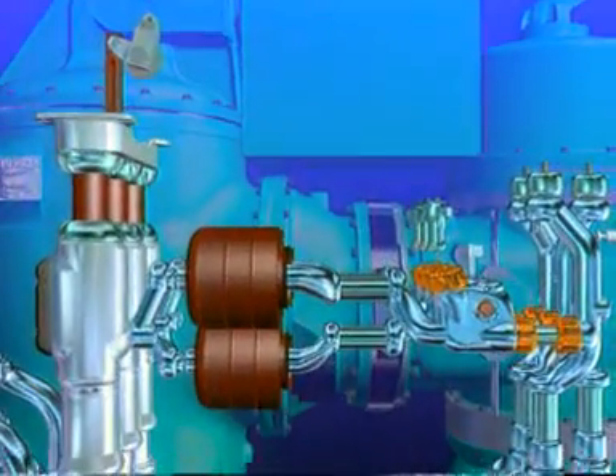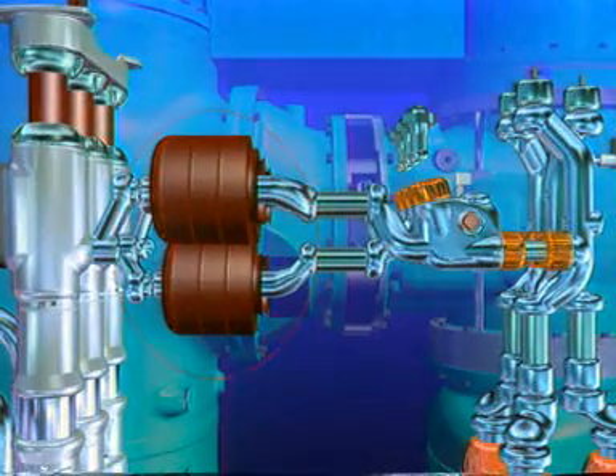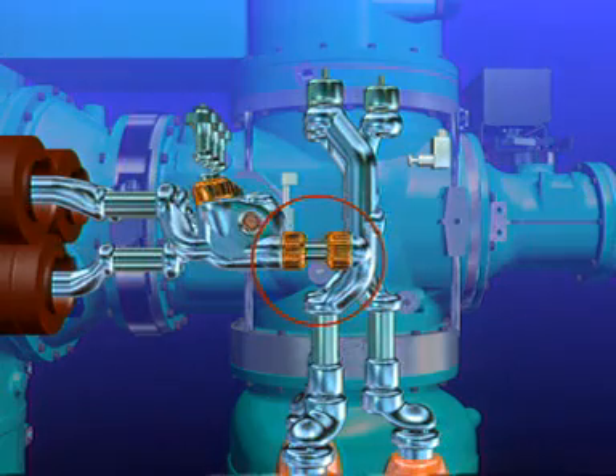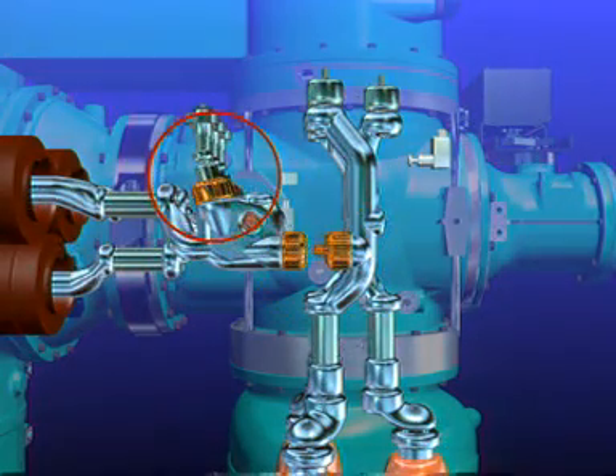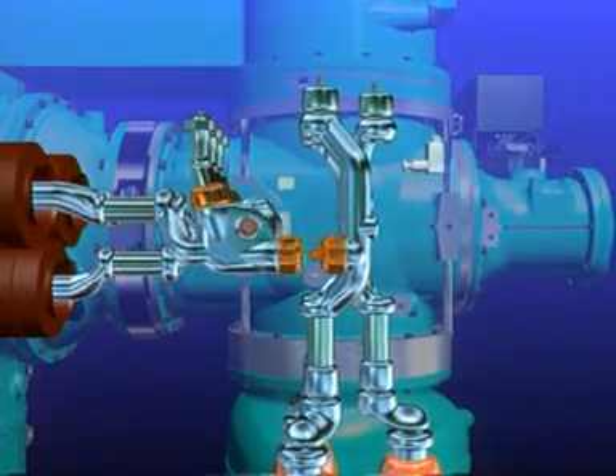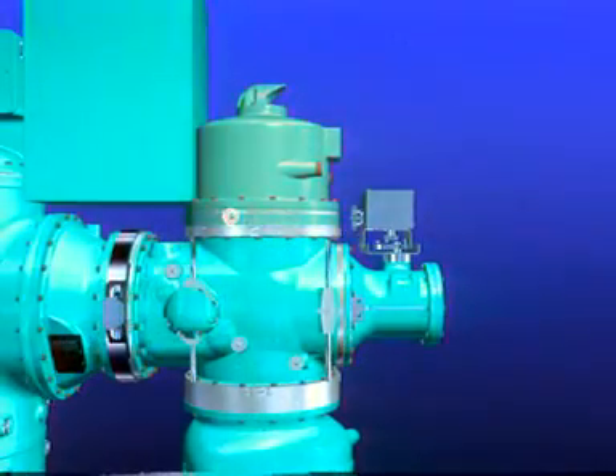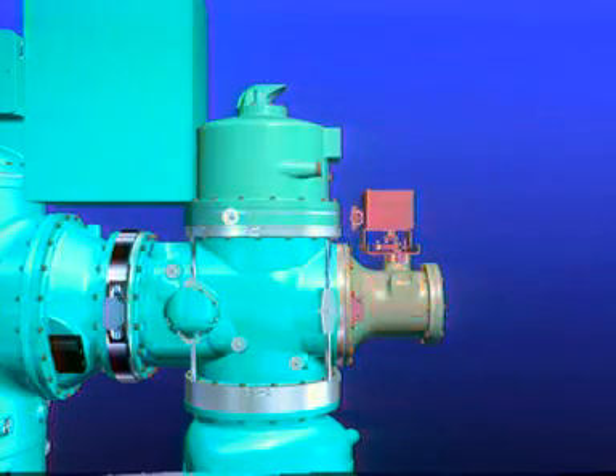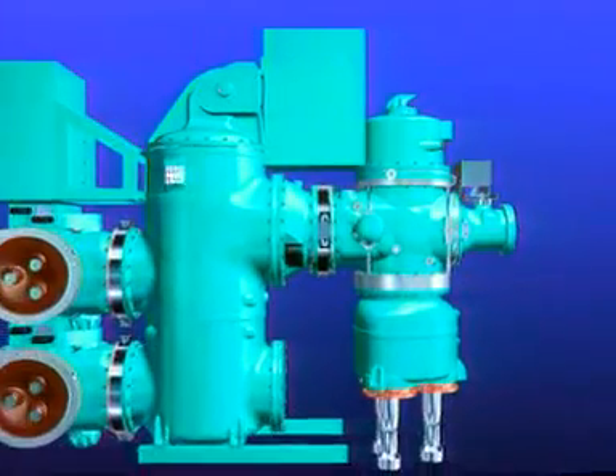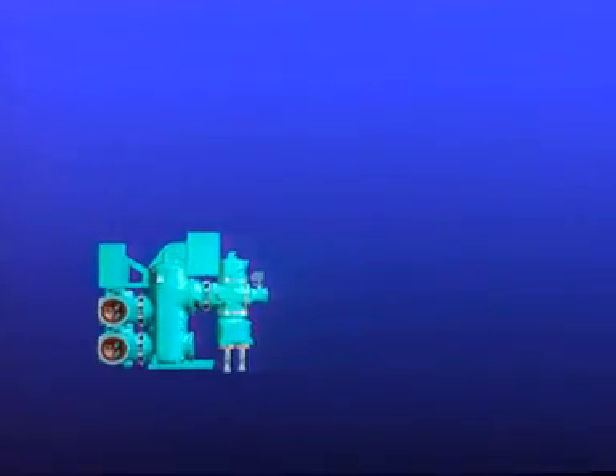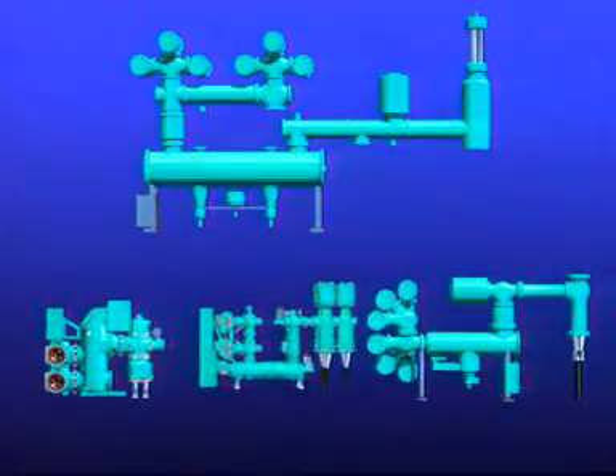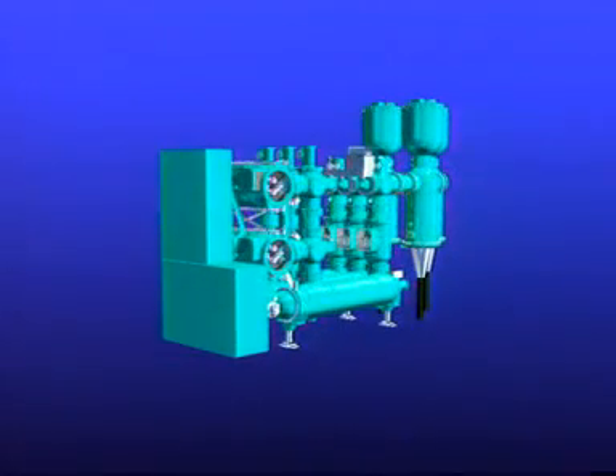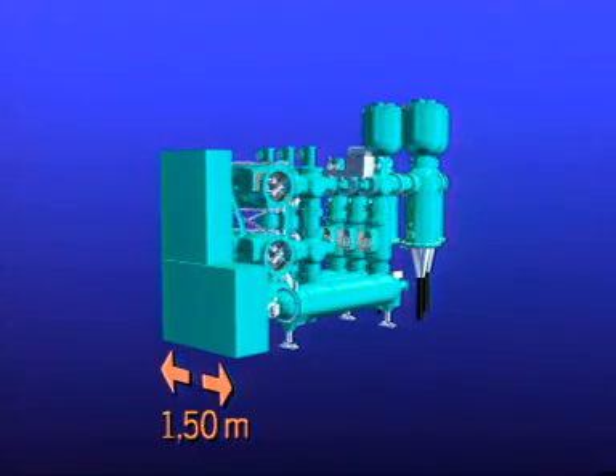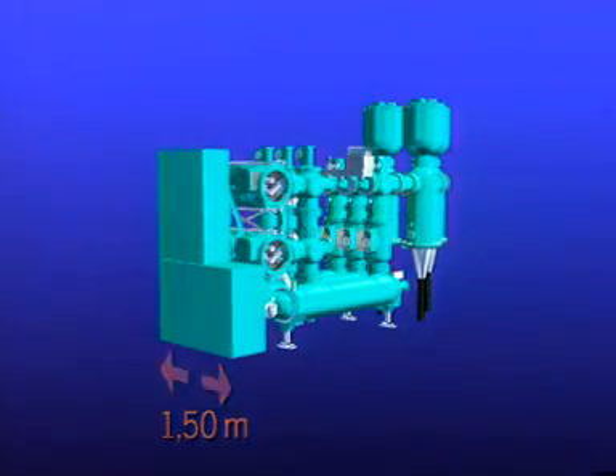In this example, a current transformer is integrated in the circuit breaker enclosure. In turn, the feeder module contains a three-position device which combines the feeder disconnector and the work-in-progress earthing switch. If required, a voltage transformer and a make-proof earthing switch can be fitted. If required, surge arresters with metal oxide resistors will limit any overvoltages occurring. The 8DN9 GIS, for rated voltages up to 245 kilovolts, which we have already described, is, with its bay width of 1.5 meters, the smallest type in its performance class in the world.